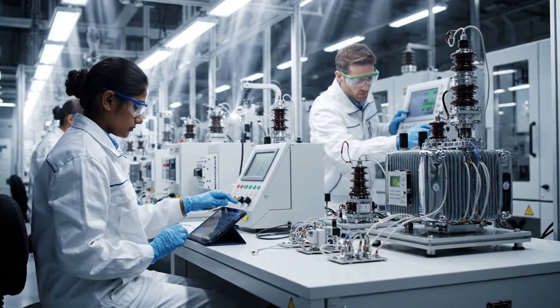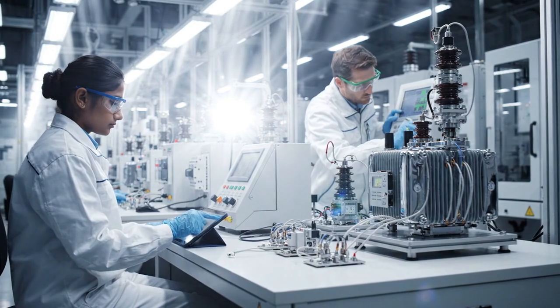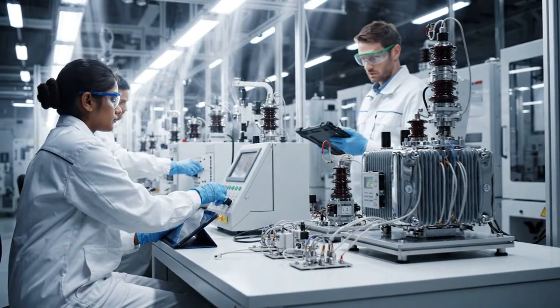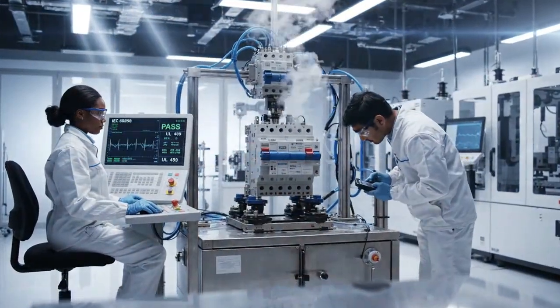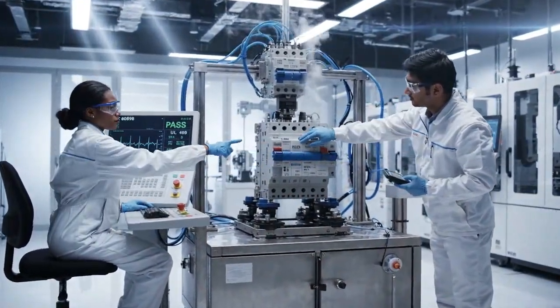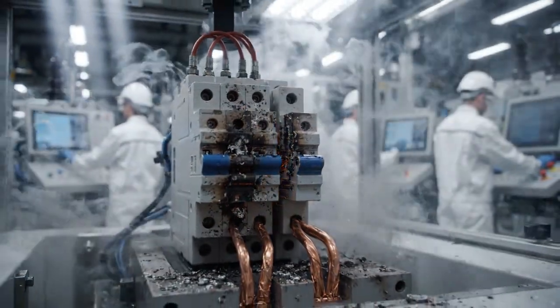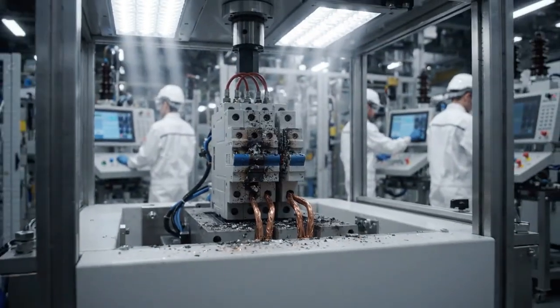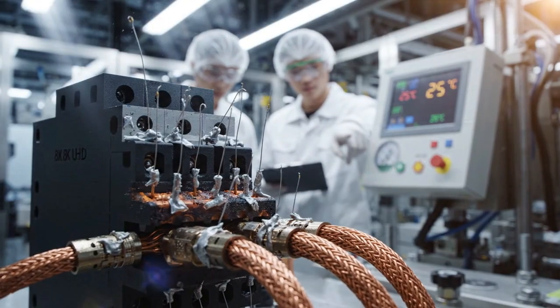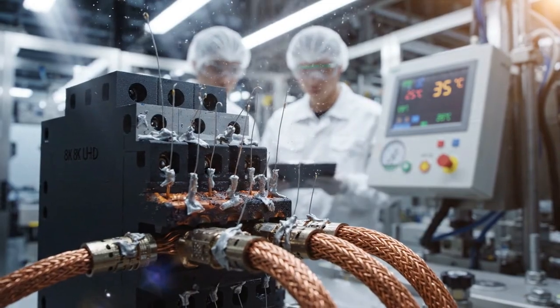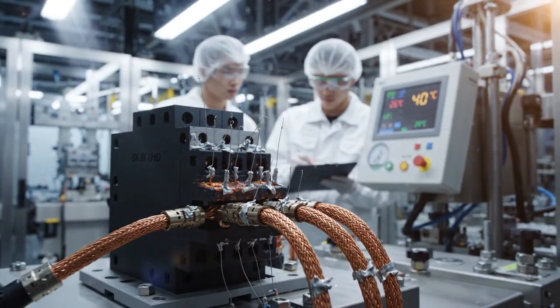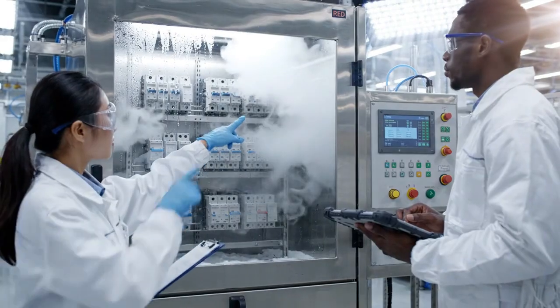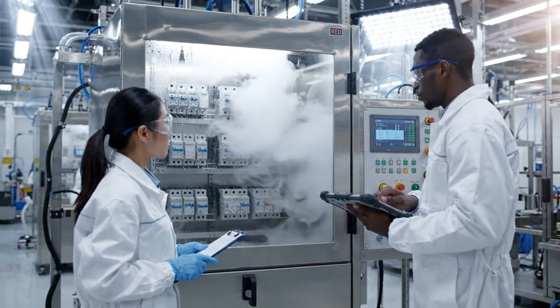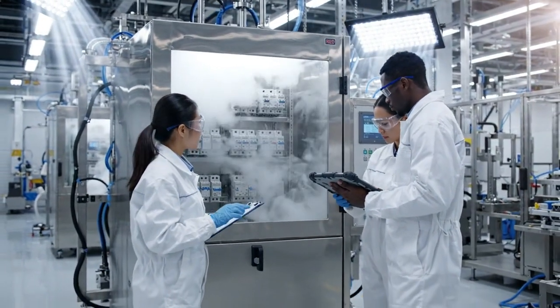Test equipment accuracy determines product quality. Regular calibration against traceable national standards ensures every breaker test produces reliable results. Type testing subjects representative samples to the complete range of tests specified by international standards, qualifying the design for production and sale. Temperature rise testing verifies that no part of the breaker exceeds its material temperature limit during continuous rated current operation. Salt spray testing simulates years of exposure to corrosive environments, verifying the breaker's plating and finish maintain protection throughout the product lifetime.